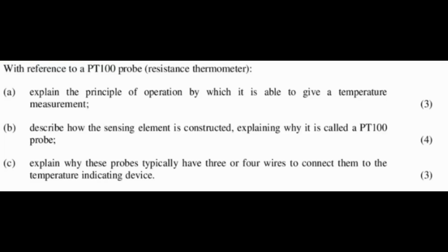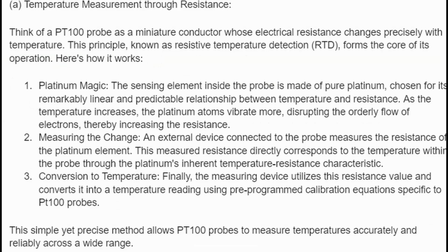With reference to a PT100 probe resistance thermometer. A. Explain the principle of operation by which it is able to give a temperature measurement. B. Describe how the sensing element is constructed, explaining why it is called a PT100 probe. C. Explain why these probes typically have 3 or 4 wires to connect them to the temperature indicating device.